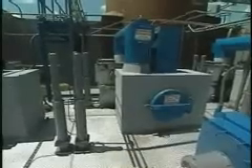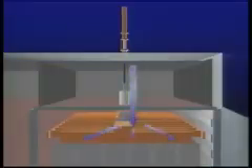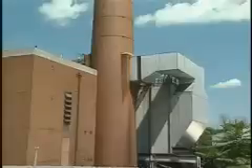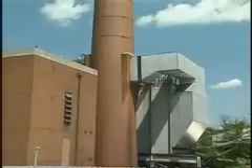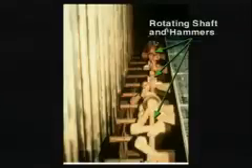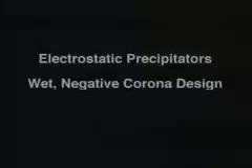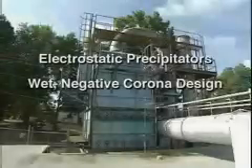For collection plate and gas distribution plate rappers, the striking energy is transmitted down a metallic rod. For discharge electrode rappers, the energy must be transmitted through an insulator rod to prevent carrying high voltage to the rapper and the accessible areas on the precipitator roof. A side-mounted rapper system has motors on the exterior of the precipitator that turn shafts running across the interior of the unit. A set of hammers is mounted to these rotating shafts to rap each individual collection plate and discharge electrode frame. For both types of rapper designs, the frequency and intensity of rapping must be carefully controlled in order to achieve proper precipitator removal efficiency.